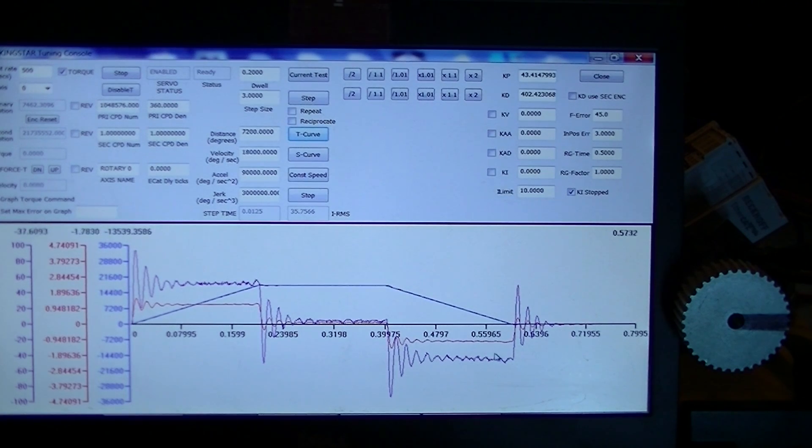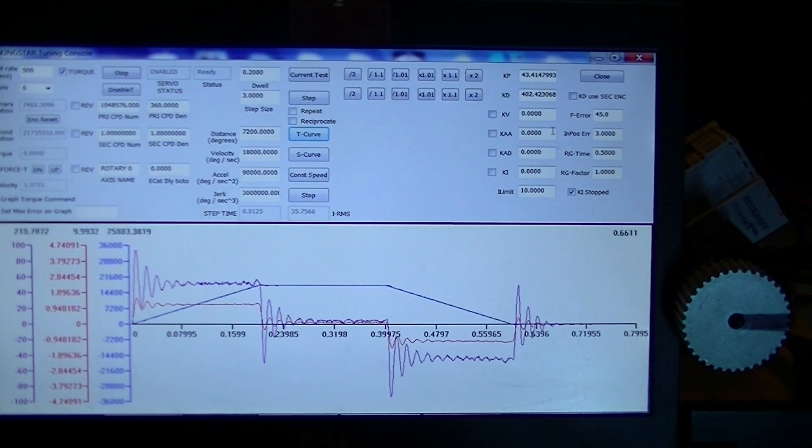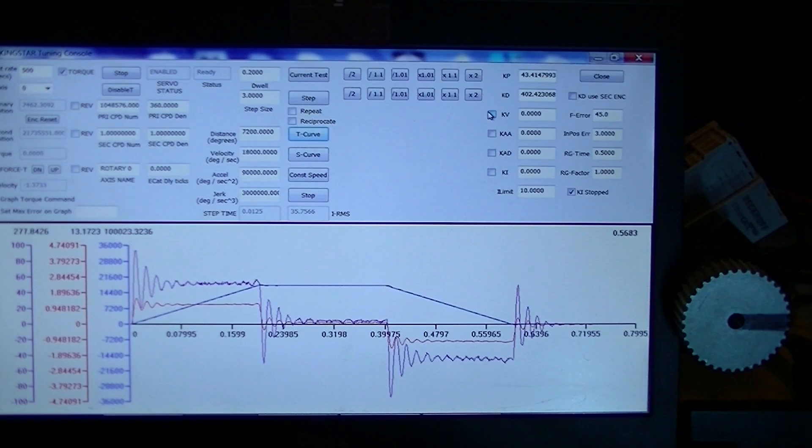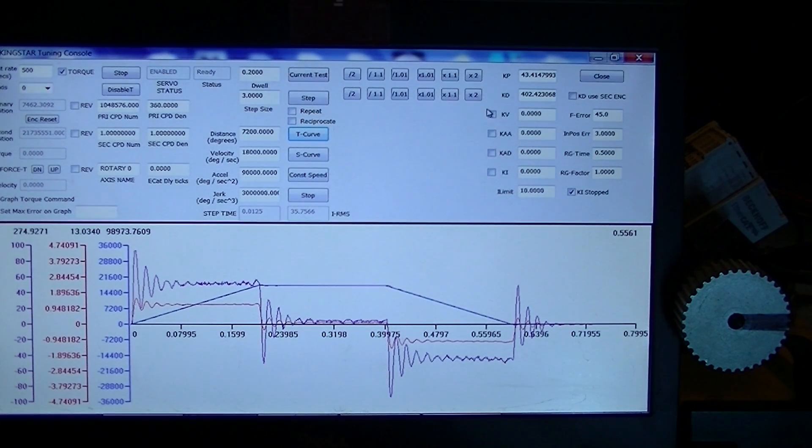What we're going to do now to try and get rid of this, we're going to go up to KV. KV basically says, I'm running at a reasonable speed. Just give me some assistance. Give me a few percentage points of torque output without requiring KP or KD to do it.